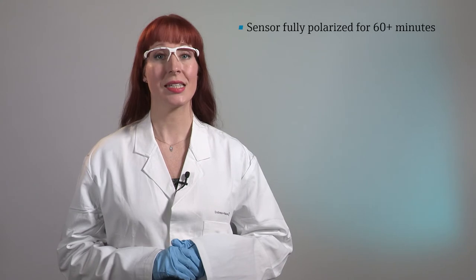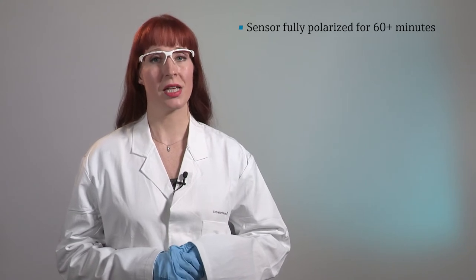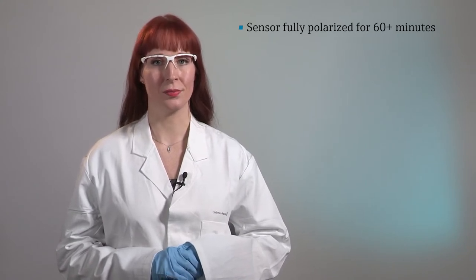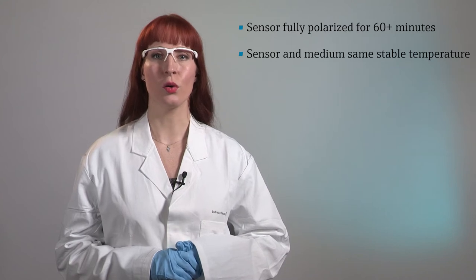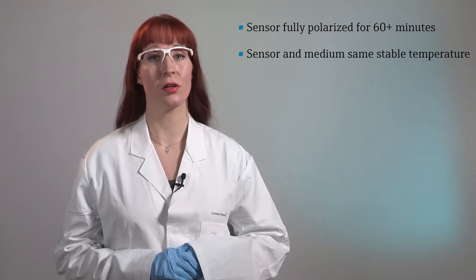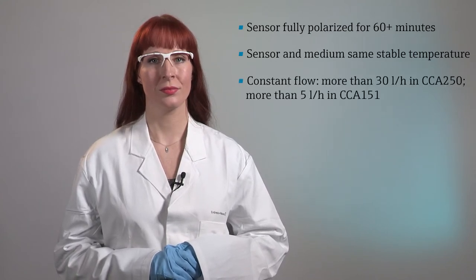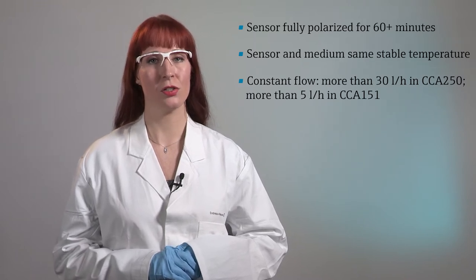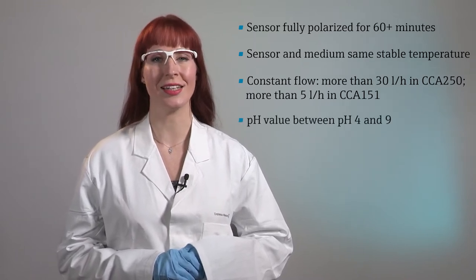The sensor must be fully polarized for at least 60 minutes. Sensor and medium must have stabilized to the same temperature. The flow must be constant and within the correct range. And the pH value must be in a range between pH 4 and 9.